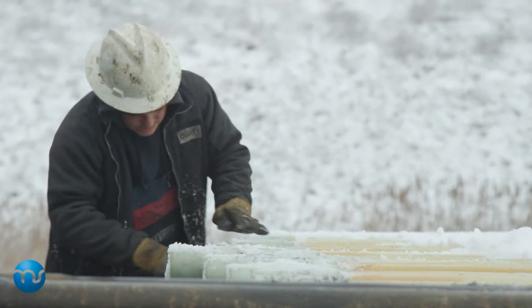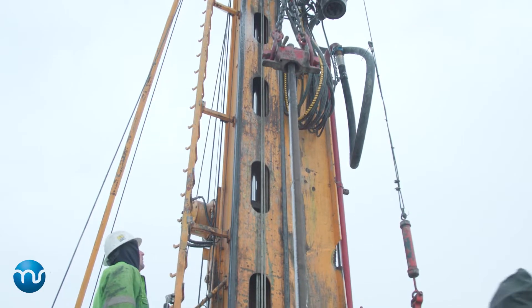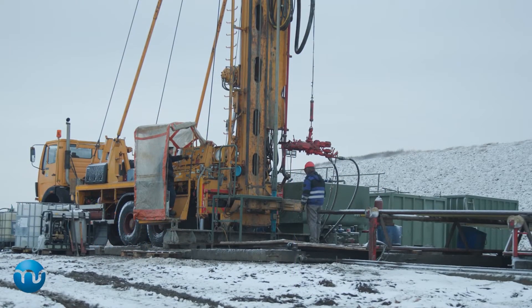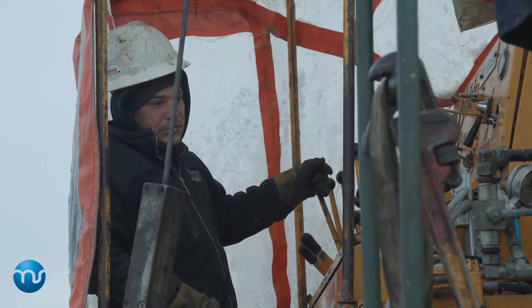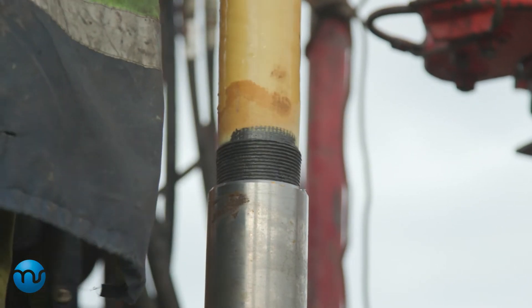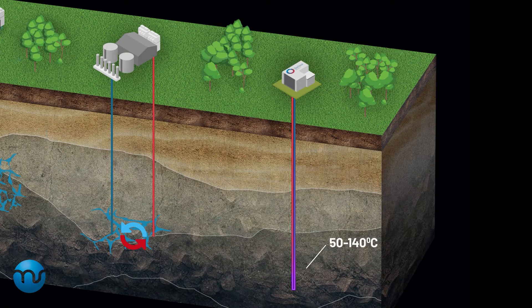The WeHeat hardware consists of individually designed modules of deep borehole heat exchangers for each well. We use an artificially added special working fluid for heat transport that collects the Earth's heat and brings it to the surface with minimal heat loss. The subsurface heat transfer takes place by conduction and convection. Water-saturated zones are mostly characterized by convection, which is a faster way of heat transfer than conduction that happens in dry rocks. In a deep geothermal probe, the whole lithological column needs to be taken into account from the surface to the bottom zone of the well. The heat of the rocks passes through the deep well structure and reaches the surface via the DBHE, Deep Borehole Heat Exchanger, installed inside the well. The amount of heat that can be generated is primarily related to the geothermal gradient and the petrophysical properties of the rocks, which can be predicted by modeling the environment.